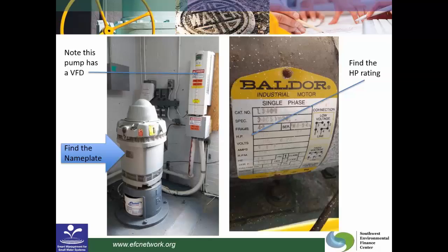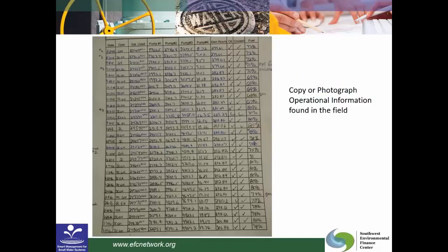And it's not always in the same place, depending on the manufacturer, but it's usually near the top, one of the first items on the list, and that's what you want to make a note of, make sure you know how many horsepower. And obviously, this nameplate is not from that pump, so it's a much larger pump than the nameplate I took a picture of. And then, as I was mentioning, the runtime data might be on a daily log. So make sure that you have access to that information, that if it's not logged into a computer, you can get copies of it made, or that you take a picture of it before you go so that you can use it in inputting data and calculating averages.